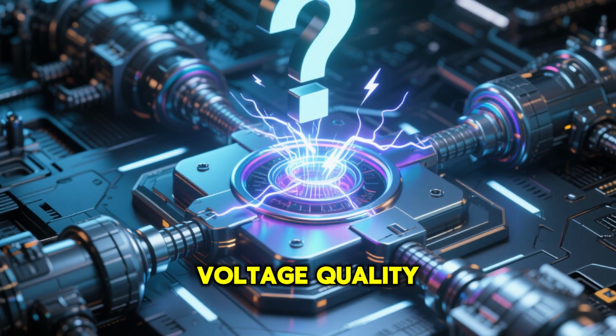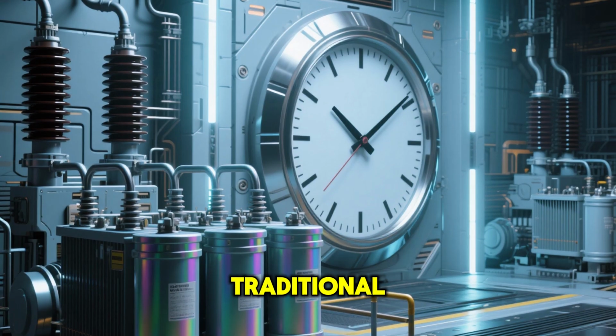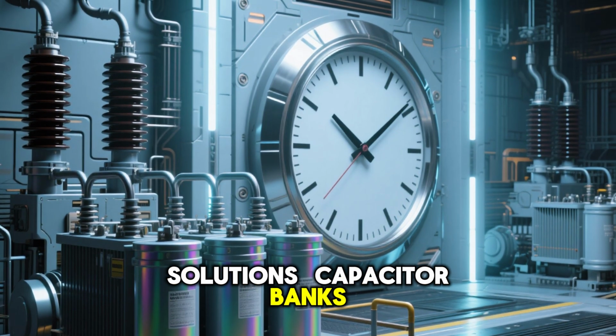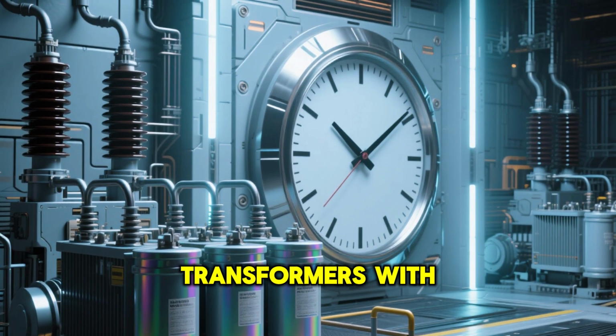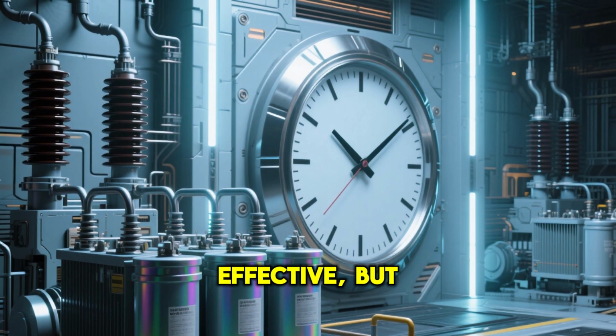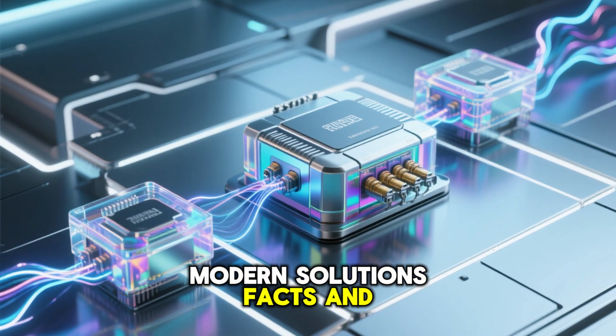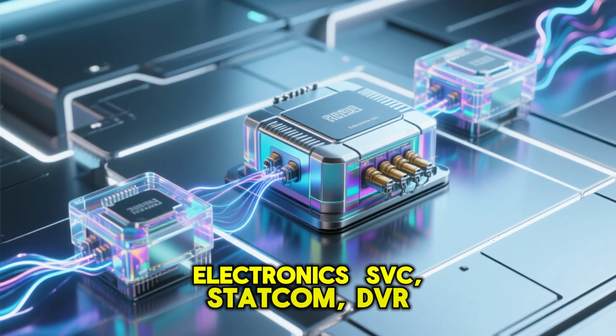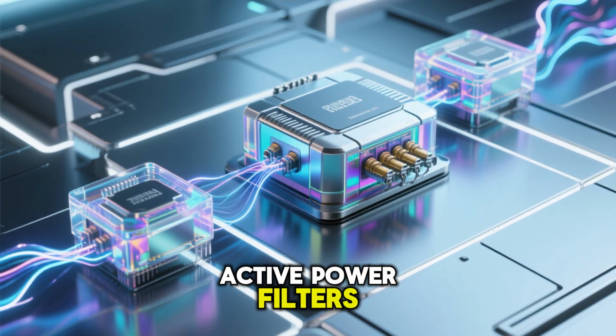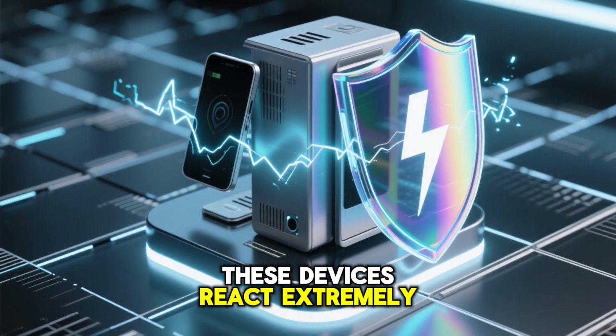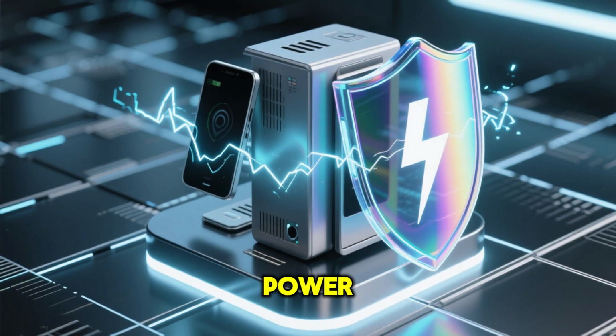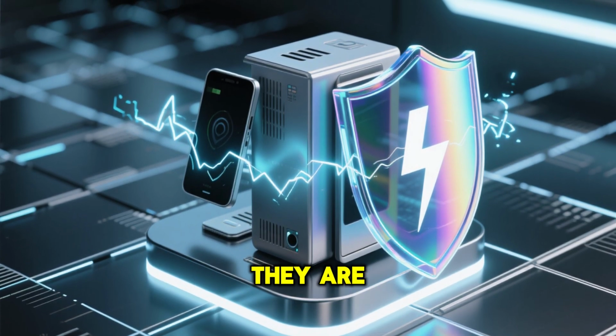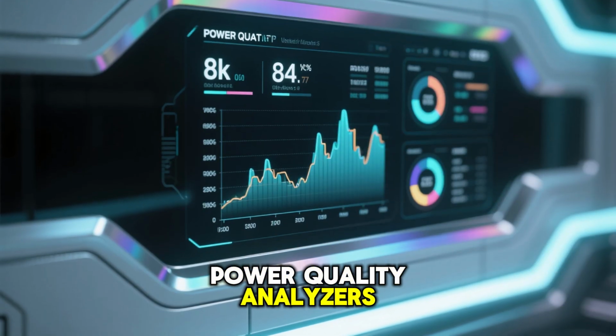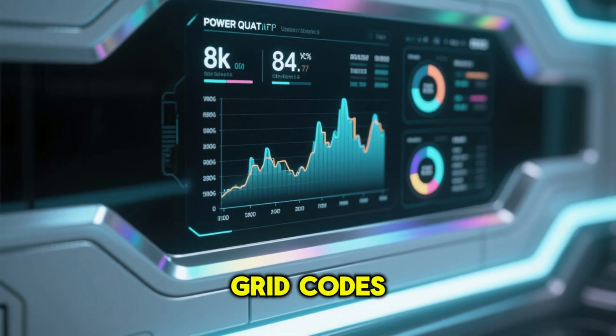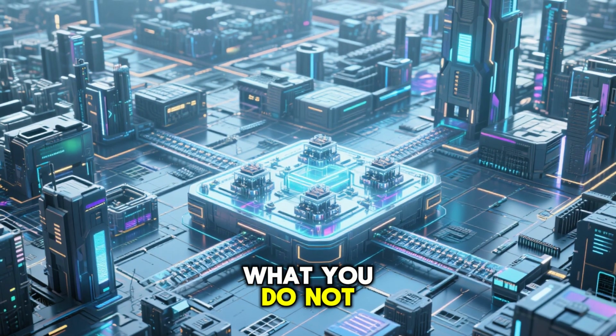How do we solve voltage quality problems? Traditional solutions: capacitor banks, voltage regulators, transformers with tap changers, effective but slow. Modern solutions: FACTS and power electronics, SVC, STATCOM, DVR, active power filters. These devices react extremely fast, inject or absorb reactive power, restore voltage dynamically. They are the immune system of modern grids. Control and monitoring: power quality analyzers, IEC 61000 standards, grid codes. You cannot control what you do not measure.